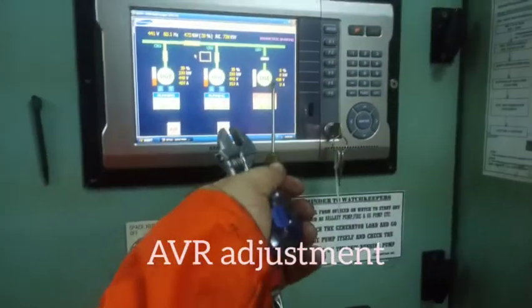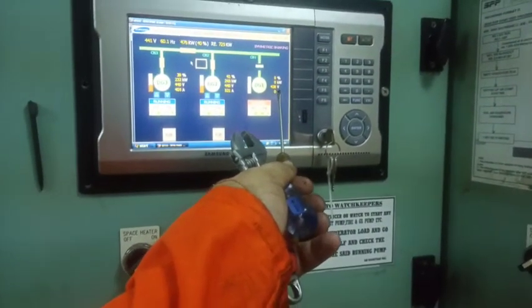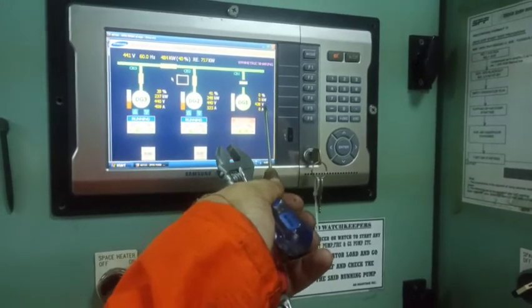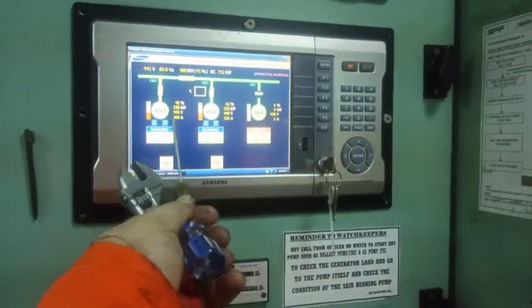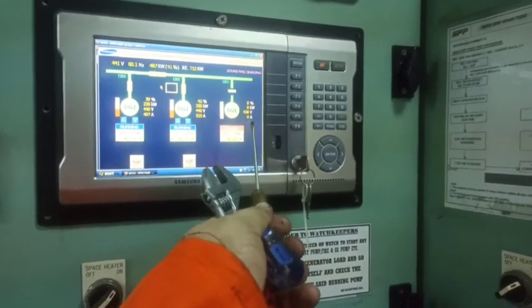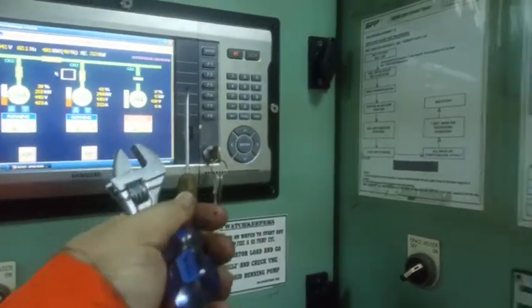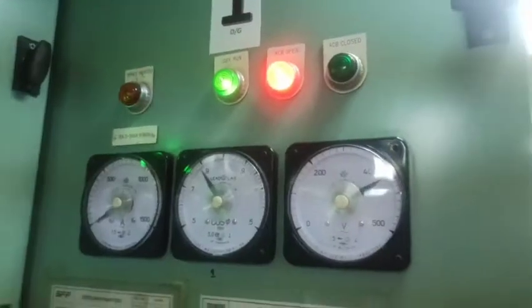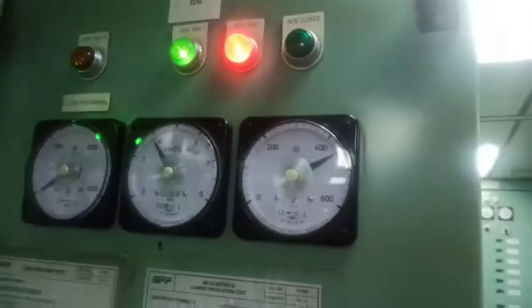It will adjust the voltage of number one diesel generator. Before it was 450. We like to be the same as the other two diesel generators for correct sharing. For this reason, we open the panel of number one, it must be working in idle position.